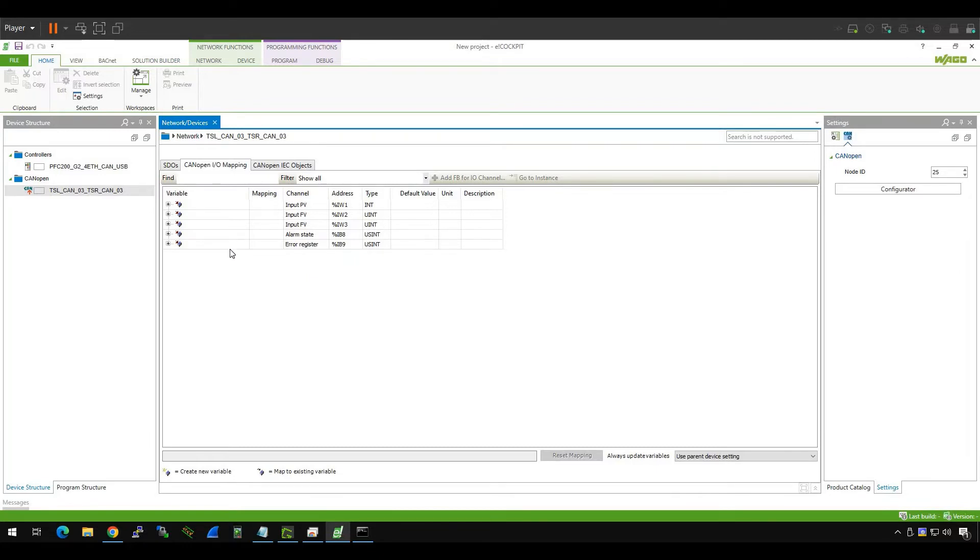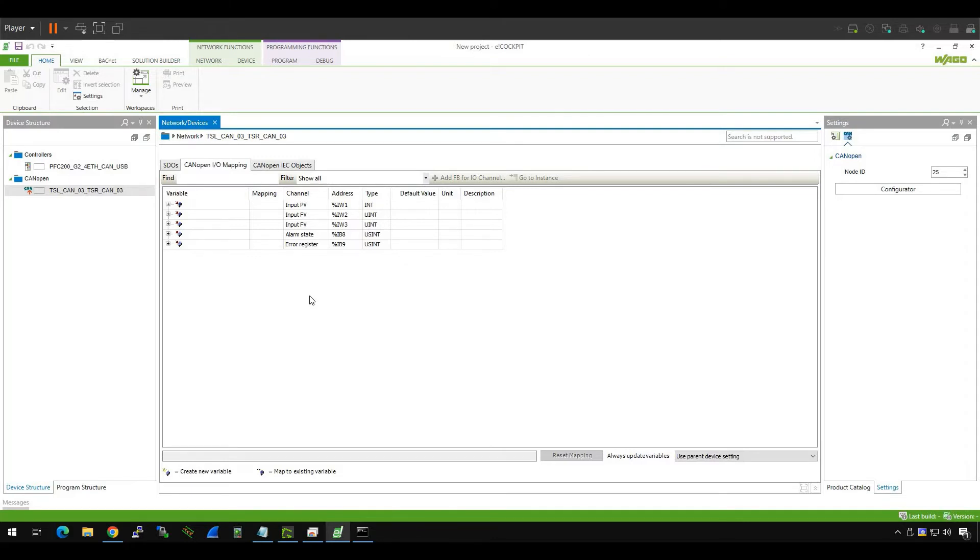Now what we need to do is map these variables inside your user program. Because in CodeSys or TwinCAT, if you don't map your process I/O inside your user program, and also if you don't use these variables inside your user program, this data will not update. It's strange, but it's like this. So here, you know that is PV, FB, alarm state, and error register. Okay, no problem.